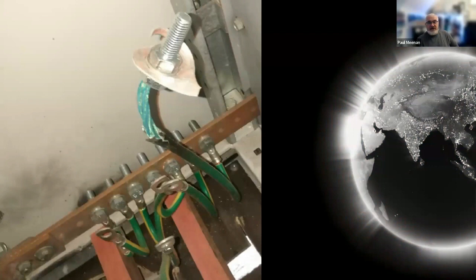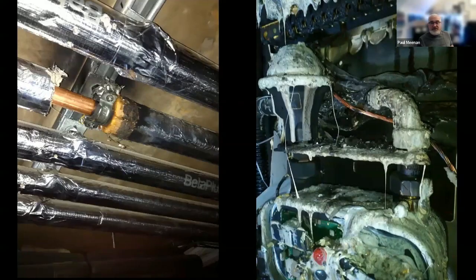One of the other things that you get on earthing is you can get some hazards. So that's a 25mm conductor that had 198 amps flowing through it. So when it goes wrong, it can go wrong terribly, which is why configuration of your earthing is key. It's very important. If you have access to clamp meters, earth leakage meters, I always recommend, and so does the IET, that before we work on earthing systems, we put a clamp on to see if there's any energy or any charge. There's 134 amps on that one, not great. And sometimes the effects of having current flowing through the earthing can be quite disastrous.